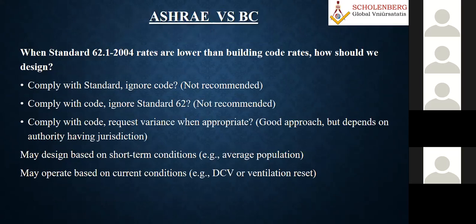Now a question will come. Sir, should I follow the ASHRAE code or the local building code? This will be the doubt everybody has, because ASHRAE 62.1, or ASHRAE 90.1, or you are talking about ASHRAE 170, and now we have a local building code. Which one should I follow for ventilation or for everything? Generally, do you always go with ASHRAE and ignore the local code? No, that is not recommended. Similarly, comply with the code and ignore the standard? That is also not recommended.